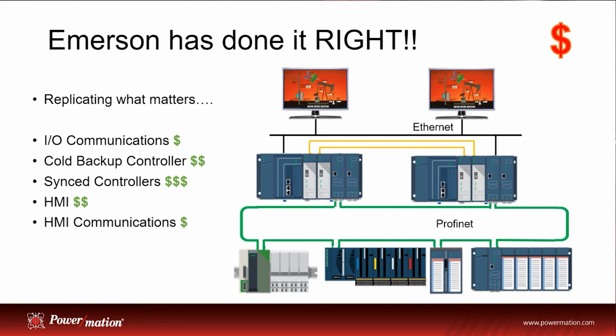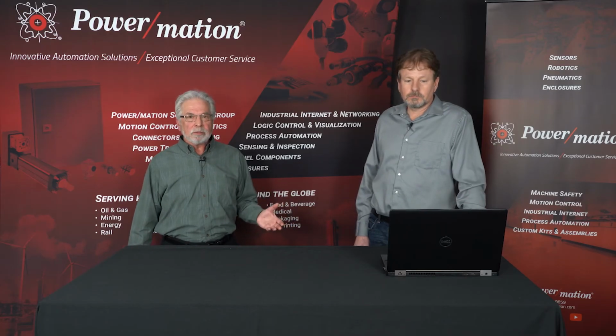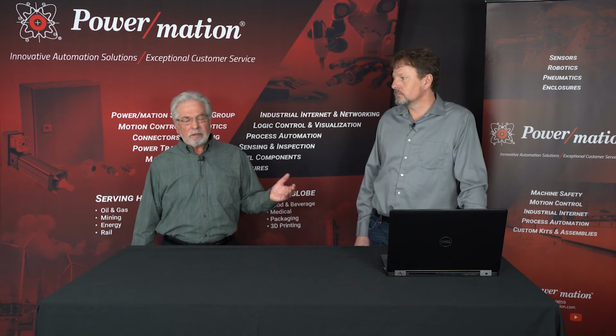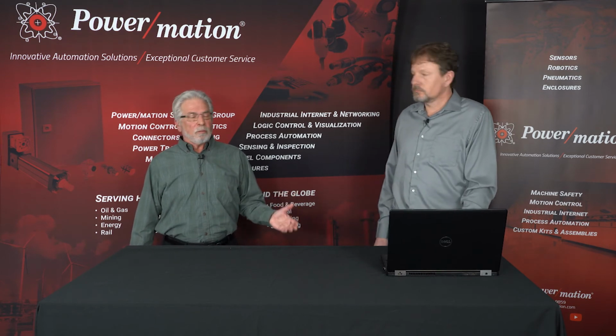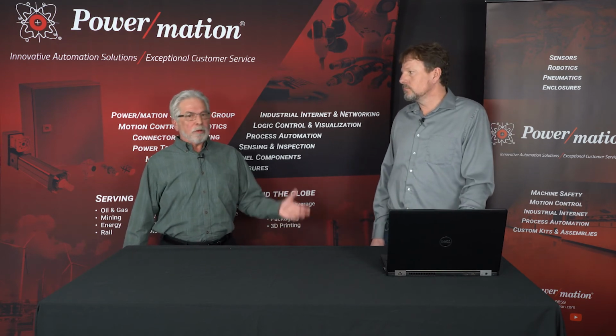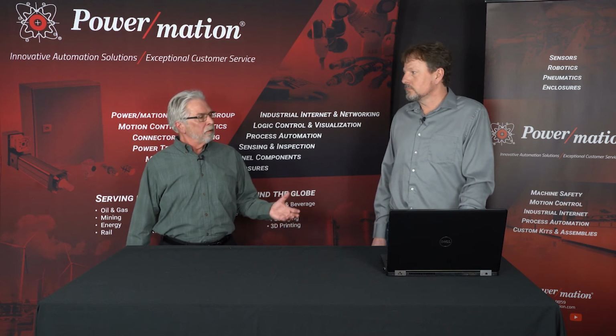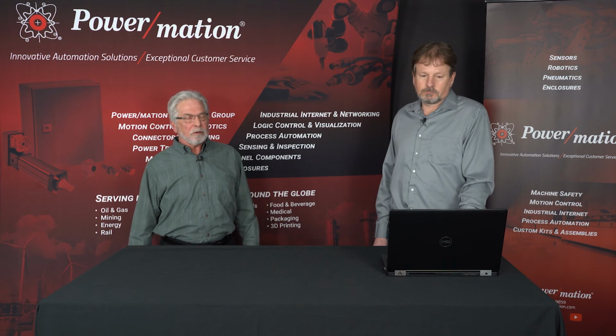We also have another solution that Emerson has that's extremely high availability, fault tolerant, and synchronized twice per scan. So the failover time of this high availability system is anywhere from 5 to 20 milliseconds. But if you can tolerate up to 300 milliseconds on a slower process, it's even less expensive because it's really the cost of a spare and a wire.